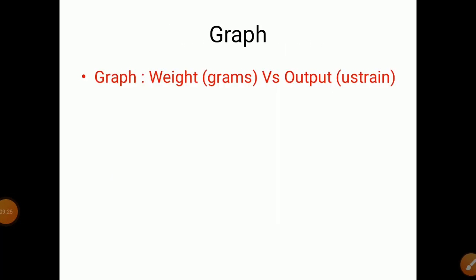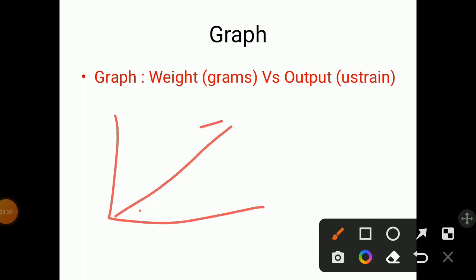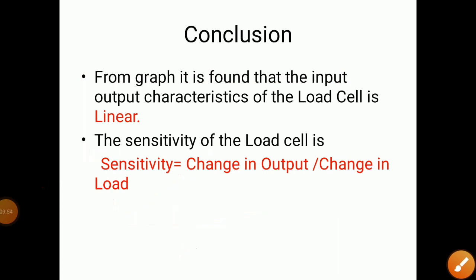From this data, we plot a graph with weight in grams on the x-axis and output in micro strains on the y-axis. The graph should be linear. From the graph, it is found that the input-output characteristics of the load cell are linear. The sensitivity of the load cell is calculated as change in output (micro strain) divided by change in load (input).